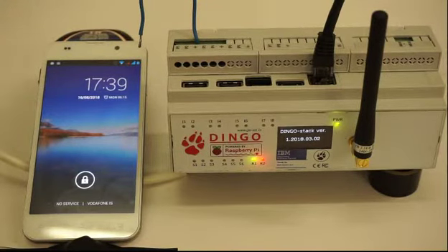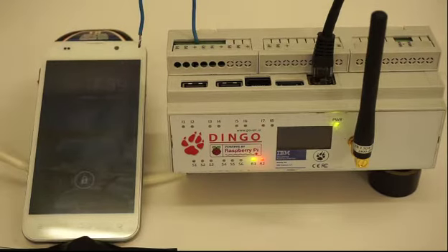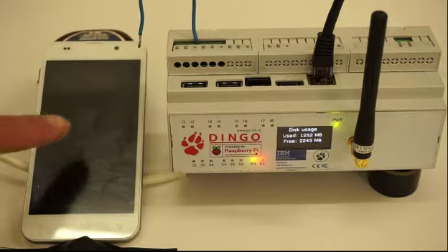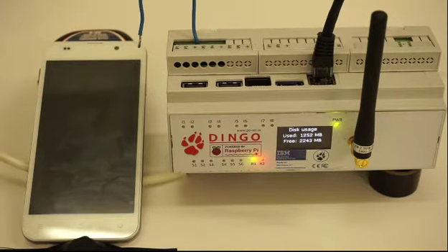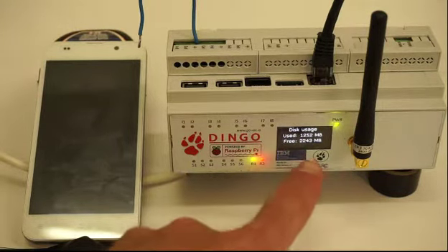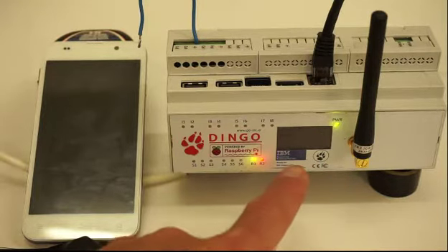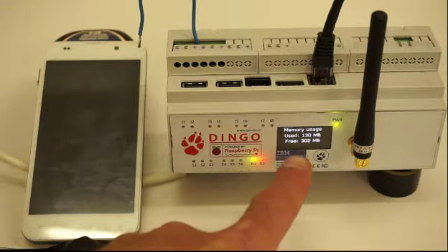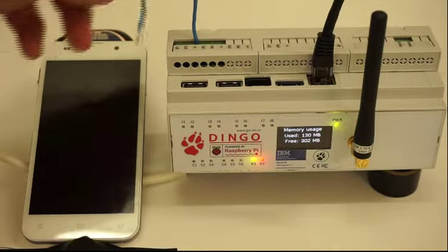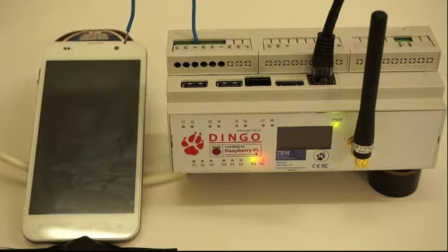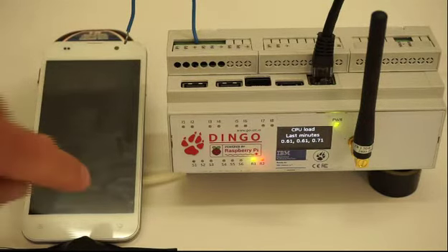Okay, here we have the Dingo just restarted, and on side of that we have my mobile phone that I'm going to use to check it out. We see that the carousel is rolling on the LCD display, and we have the Ethernet out here, of course, and here I have some wire to connect to the ground to one of the binary inputs for testing the binary inputs. So let's first test the binary inputs and see if we get the LEDs glowing there.